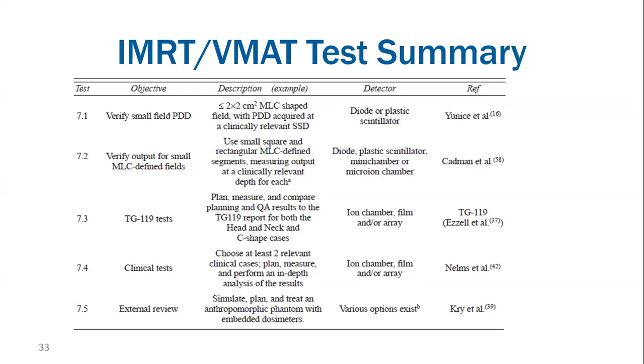A few important recommendations that they make also hold for the TG119 tests that we have been talking about all along. So the range of optimization parameters, namely the amount of modulation, the minimum field size, and the types of plans that you use clinically during commissioning should be clearly documented and representative of clinical practice, right? You don't want to be treating with these super modulated plans when you commissioned these kind of easy low level modulation plans. They also say that in general, more time should be devoted to fine tuning the model for the highly modulated plans. Simple plans are typically much less influenced by the often changed parameters, particularly the parameters related to your MLC model.